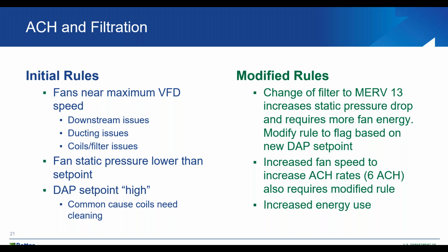Here's another example. We talked about outside air conditions. Well, another way to modify conditions under COVID is through ACH, air change per hour, rate increases, as well as additional filtration. So rules are created to find the faults within the operating conditions. For example, is a single VAV box driving pressure at the air handling unit? Well, it'll flag because it's potentially looking at the VAV box as well as looking at the air handler and indicating that the VFD is running close to maximum speed.